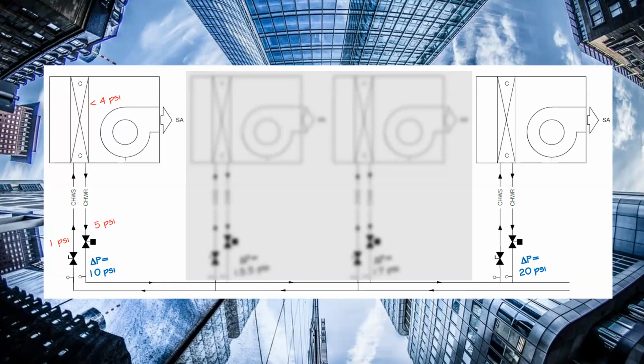Now let's take a look at that close zone. So that balancing valve that was taking up 12 psi is now seeing 2 pounds of pressure drop across it. We still have less than 4 pounds on that coil, but for conversation's sake, we'll say that it's 4. That means that we have a massive overflow on that valve of 10 pounds, and we have poor valve authority caused by that overflow. It makes it almost impossible to control that valve at low loads in these spaces.